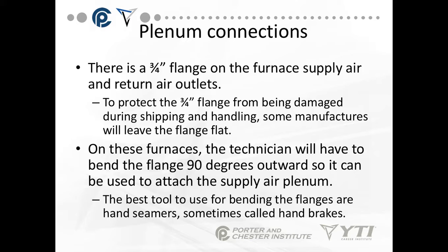For plenum connectors, there's a 3/4 inch flange on the furnace supply and return ducts. To protect the flange from being damaged during shipping and handling, some manufacturers leave the flange flat. On these furnaces, the technician will have to bend the flange 90 degrees outward so it can be used to attach the supply air plenum. The best tool for bending the flanges are hand seamers, sometimes called hand brakes.